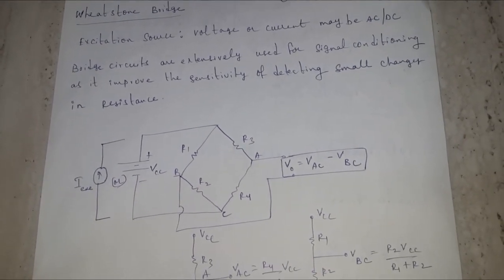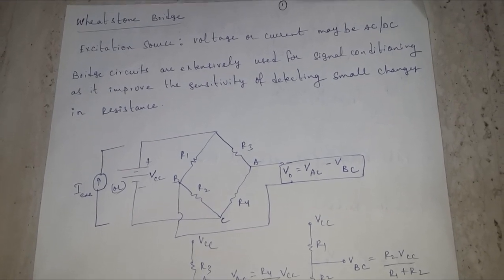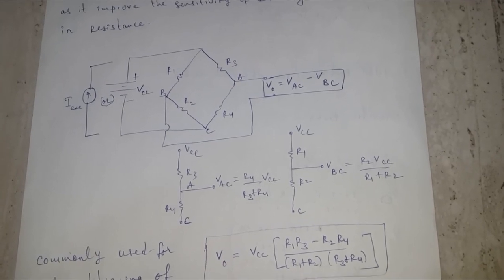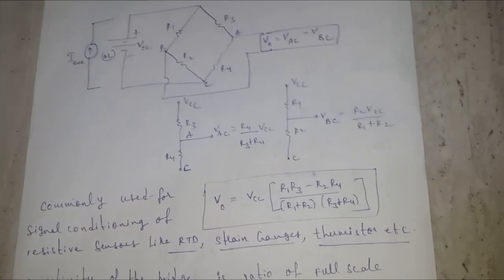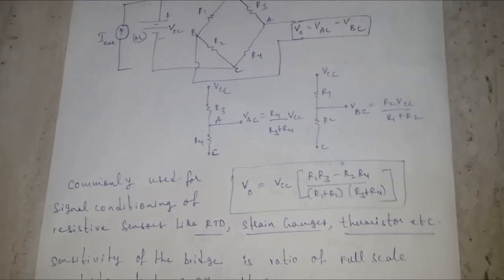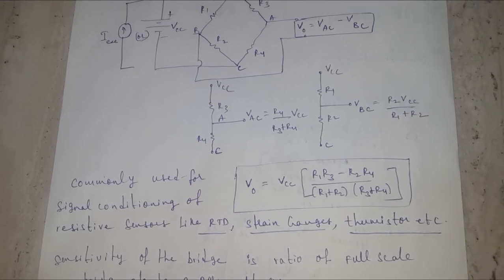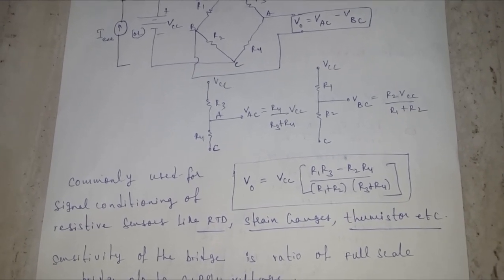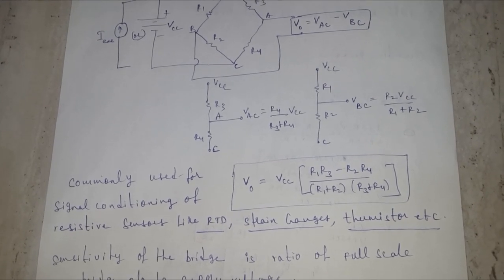The excitation can be a current source or a voltage source, and it may be AC or DC. If you see this Wheatstone bridge, the output equation when derived gives V_out equal to VCC times (R1·R3 minus R2·R4) divided by the denominator. This is a commonly used signal conditioning circuit for resistive sensors.